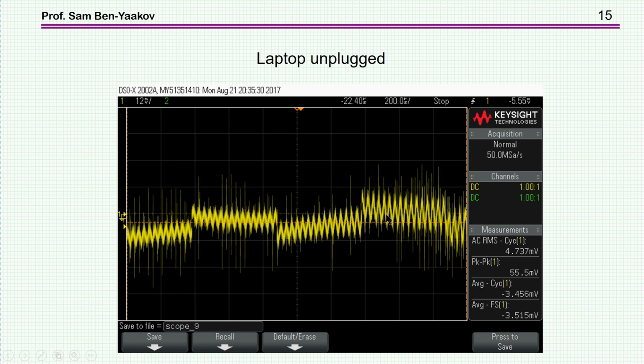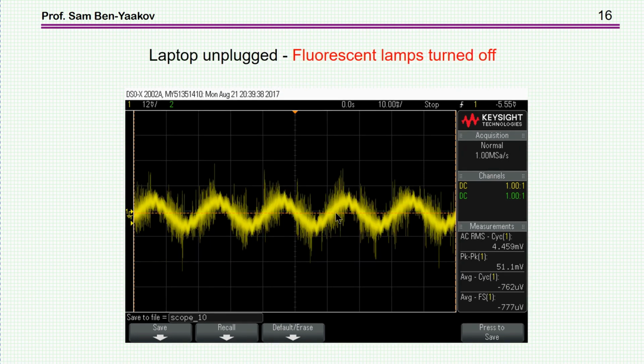So this is probably coming from outside. Indeed, at around 20-25 kilohertz it resembles the frequency of a fluorescent lamp's electronic ballast. So we turned off all the fluorescent lamps in the room, and indeed this high frequency component disappeared. So the high frequency component we saw has nothing to do with the laptop's operation - it's coming from outside, from the lamp.